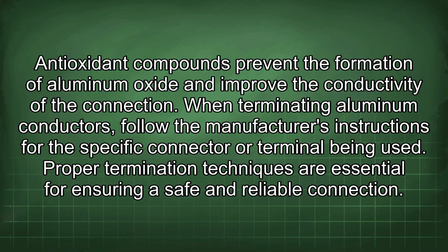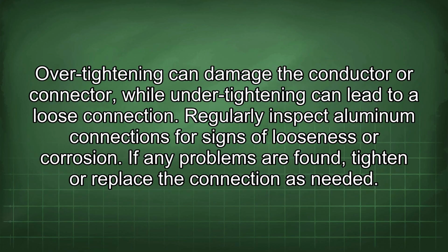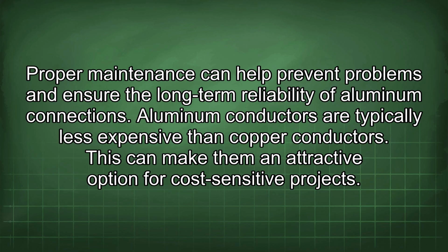When terminating aluminum conductors, follow the manufacturer's instructions for the specific connector or terminal being used. Proper termination techniques are essential for ensuring a safe and reliable connection. Over-tightening can damage the conductor or connector, while under-tightening can lead to a loose connection. Regularly inspect aluminum connections for signs of looseness or corrosion. If any problems are found, tighten or replace the connection as needed. Proper maintenance can help prevent problems and ensure the long-term reliability of aluminum connections.